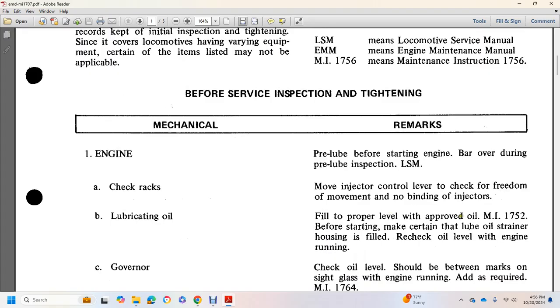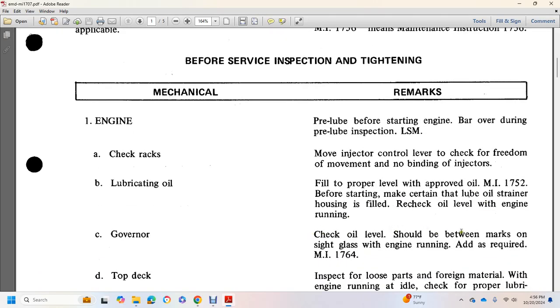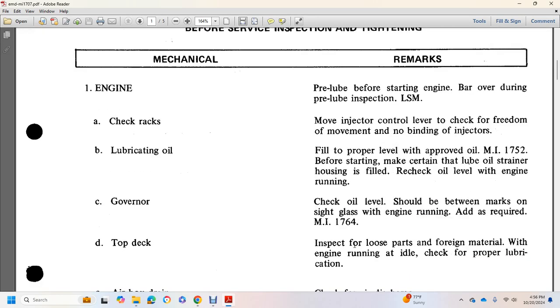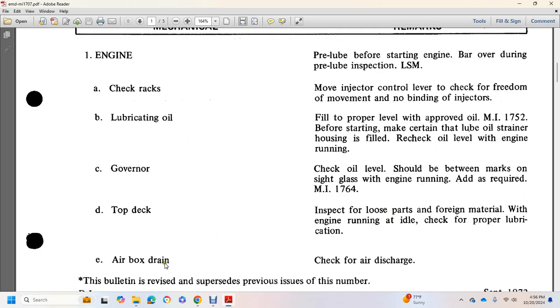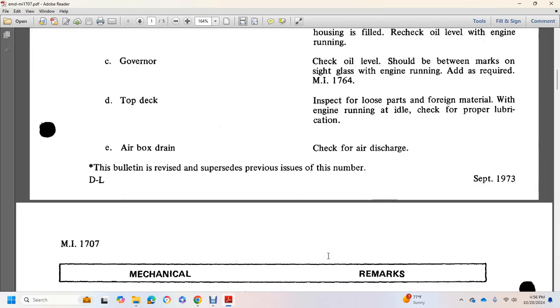Lubricating oil, fill to proper level, refer to Maintenance Instruction 1752. Before starting, make certain the lube oil strainer housing is filled, and recheck the oil level with the engine running. Governor, check the oil level, which should be between the marks on the sight glass with the engine running, as required, Maintenance Instruction 1764. Top deck, inspect for loose parts and foreign material. With the engine running at idle, check for proper lubrication. Airbox drain, check for air discharge.